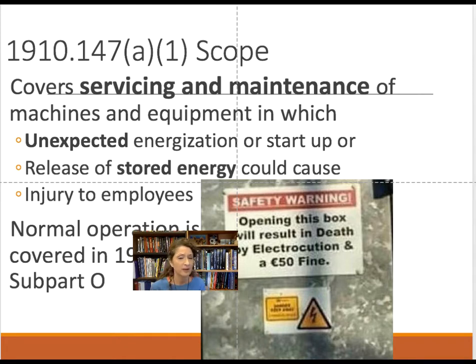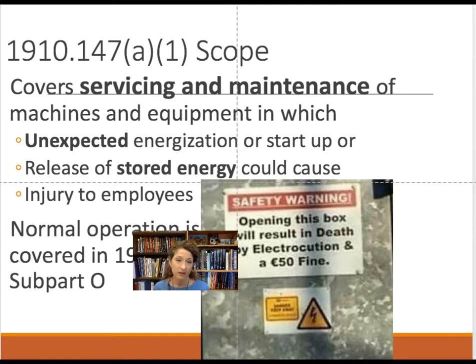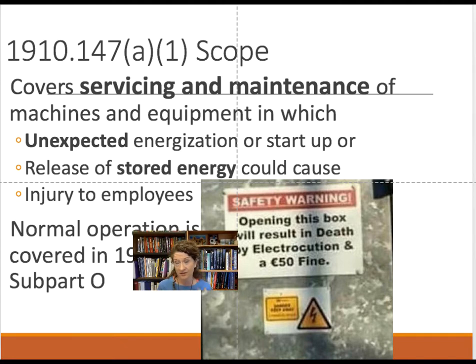The scope of lockout-tagout differs from machine guarding. Machine guarding applies when the machine is running during normal operations — for example, using a saw to cut something. Lockout-tagout covers the servicing of equipment, when there's maintenance going on and equipment must be completely shut down. It prevents the unexpected re-energization of machinery, as well as the release of any stored energy.